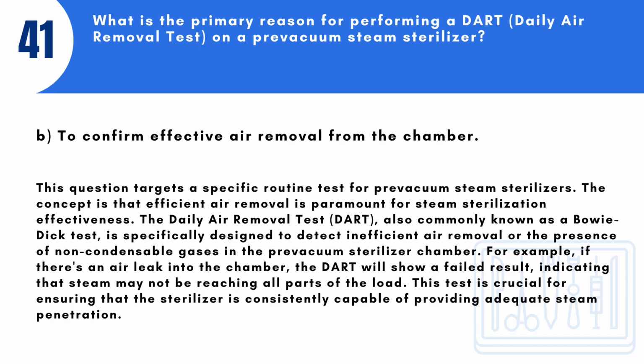For example, if there's an air leak into the chamber, the DART will show a failed result, indicating that steam may not be reaching all parts of the load. This test is crucial for ensuring that the sterilizer is consistently capable of providing adequate steam penetration.